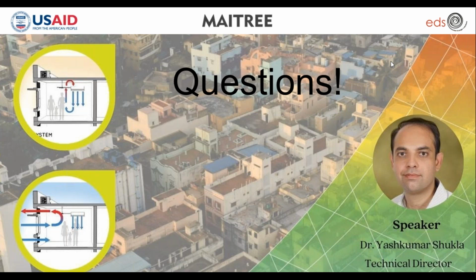It's a long, but it's a multi-layered question, I would say. So ASHRAE 55's adaptive model is only proposed for natural ventilation, so that's true. However, recent studies have shown that mixed mode buildings, where you combine natural ventilation and air conditioning and change the operation mode, would also be able to use adaptive comfort mode. So sufficient evidence exists that you do not always have to rely on the PMV method to size mixed mode buildings.